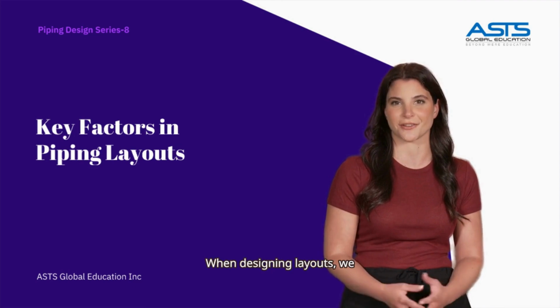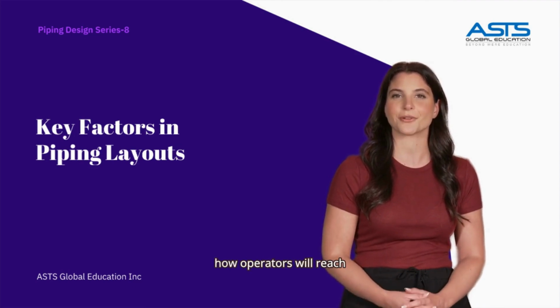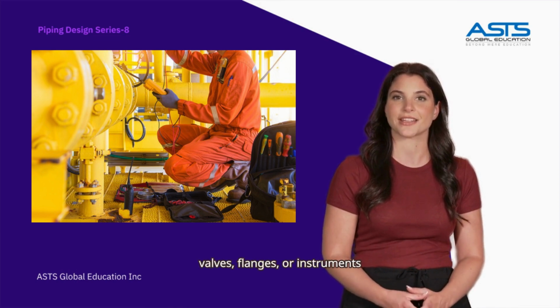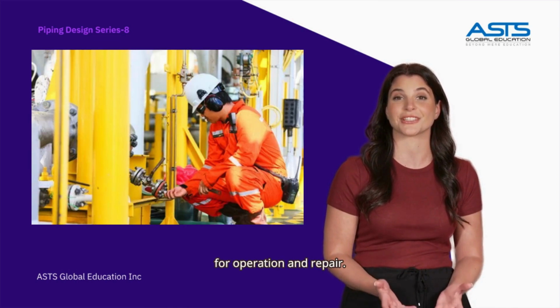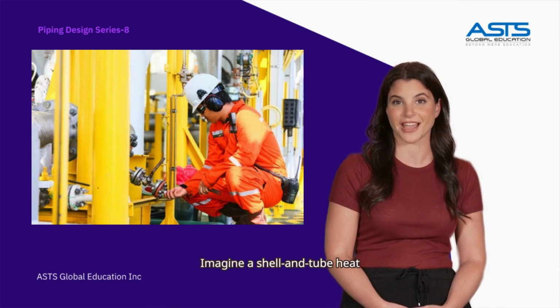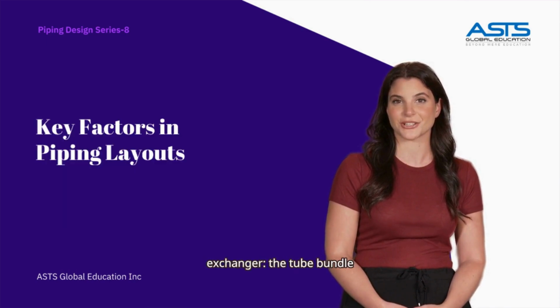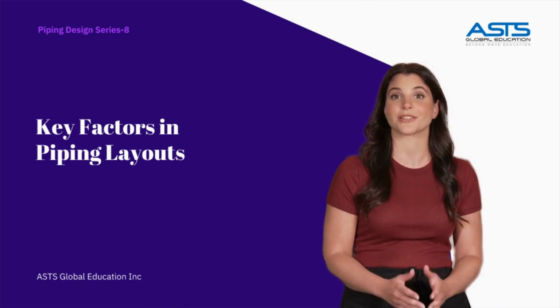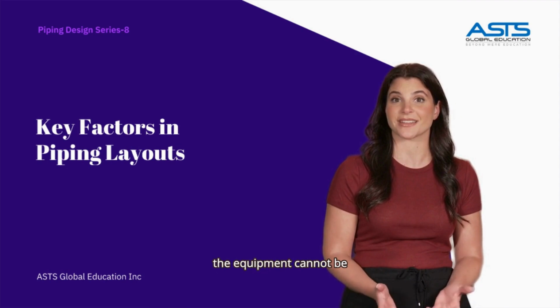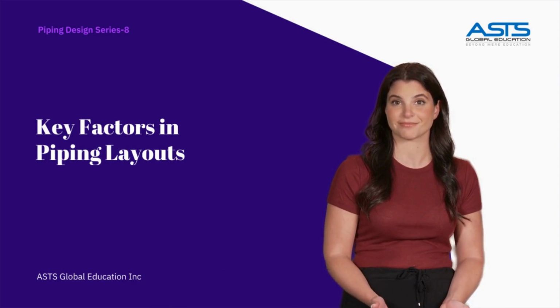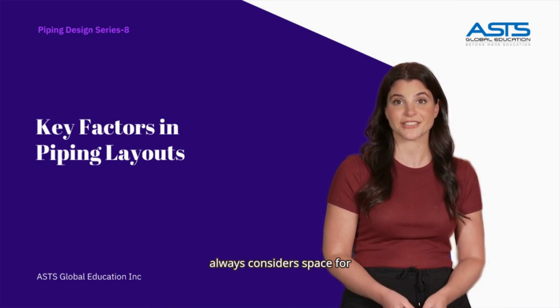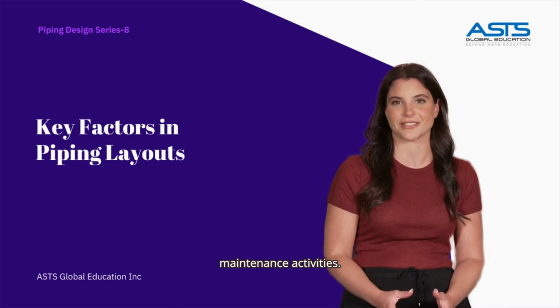Maintenance and accessibility are also critical. When designing layouts, we need to think about how operators will reach valves, flanges, or instruments for operation and repair. Imagine a shell and tube heat exchanger. The tube bundle inside has to be removed for cleaning or replacement. If the piping blocks the removal space, then the equipment cannot be maintained properly. A good piping layout always considers space for maintenance activities.